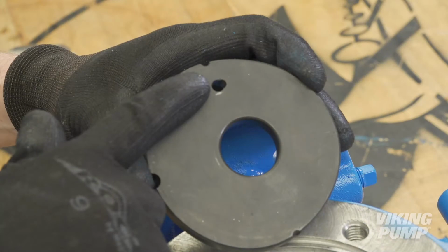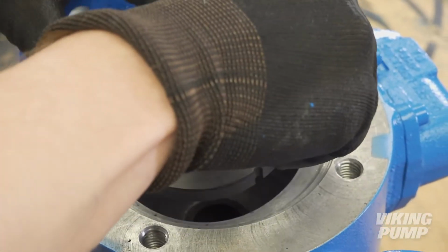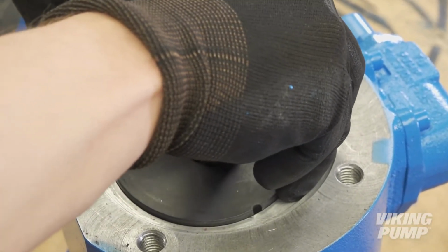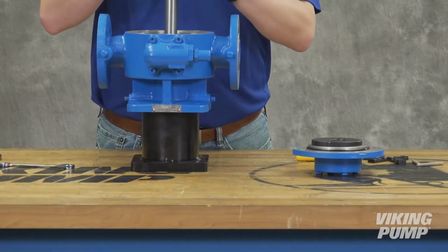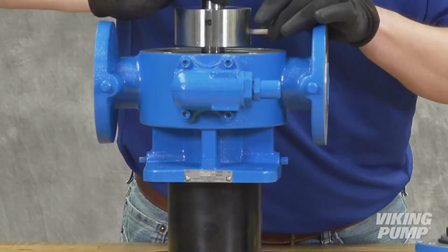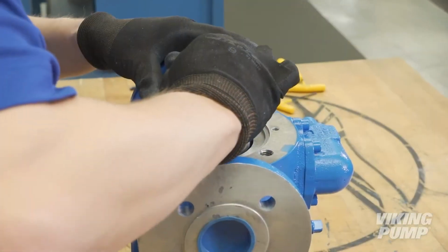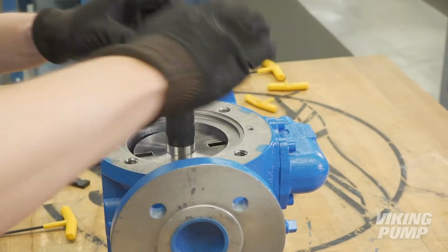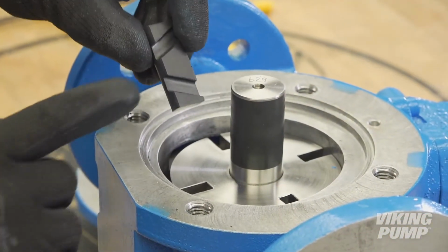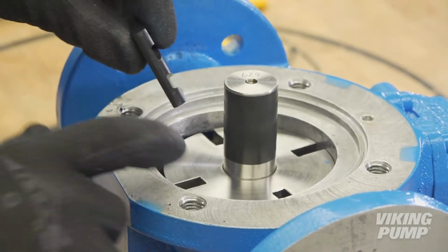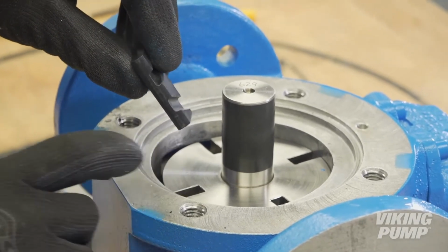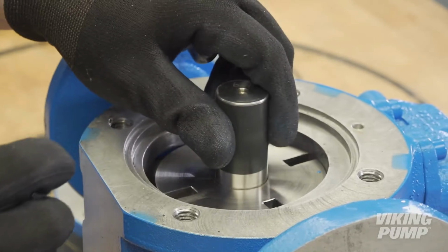Reinstall each component, making sure to flip the two carbon discs so that the holes line up with the open holes on the suction side of the pump. When reinstalling the vanes, make sure the grooved face of each vane is in the new direction of rotation or on the leading side of each vane.